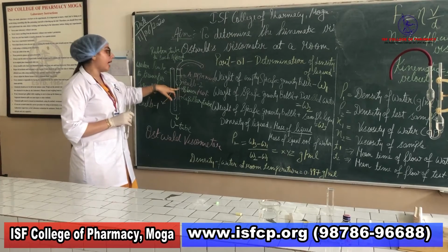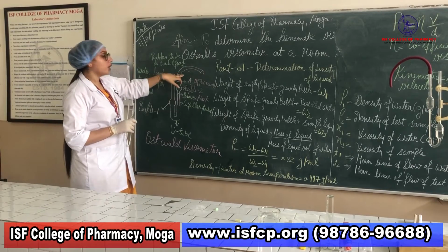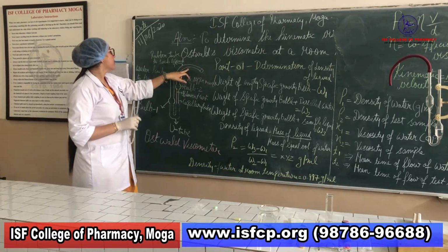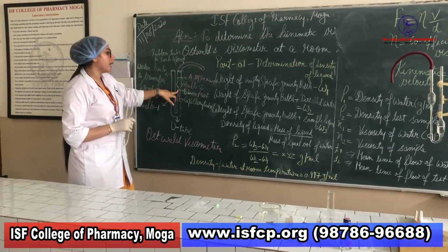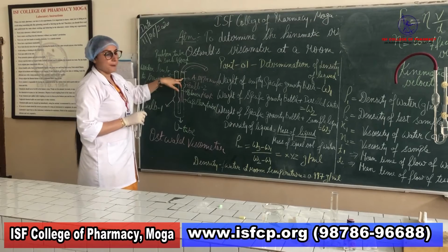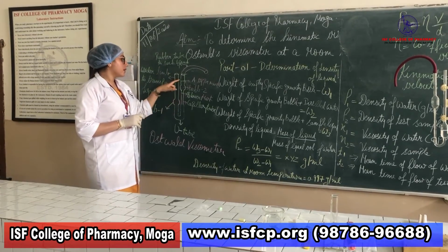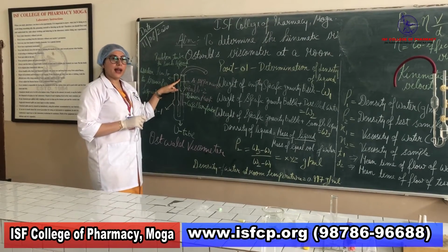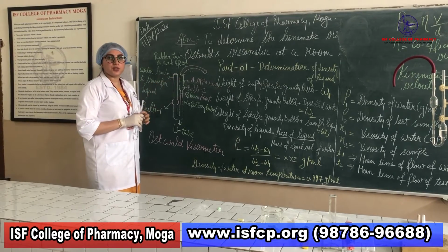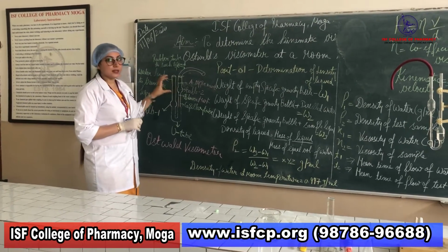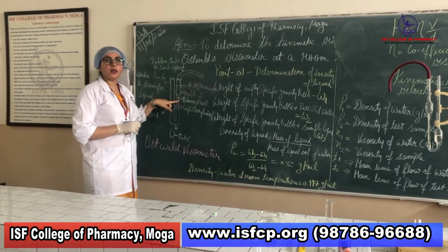The lower mark is B and the upper mark is A. Above the second part of the capillary tube there is a rubber tube to suck the liquid from point B of the capillary tube up to mark A, the upper mark. When sufficient liquid has been sucked above point A, start your stopwatch, let the fluid flow from point A to point B, and record the time.